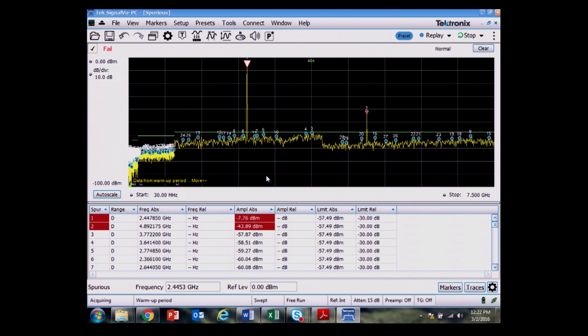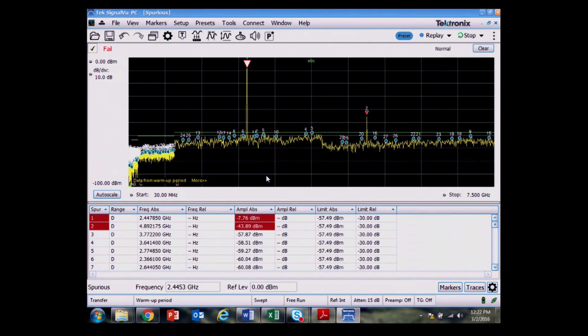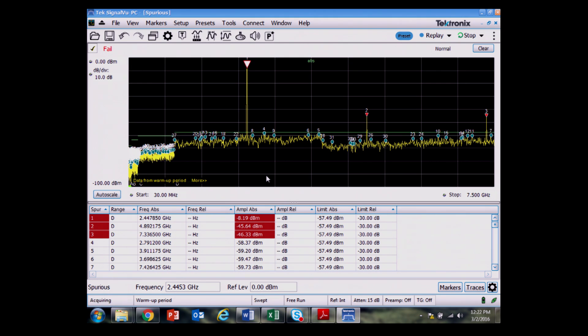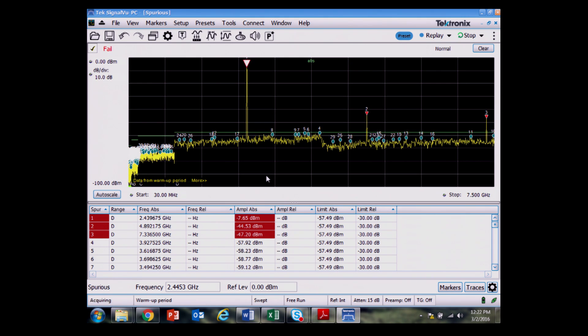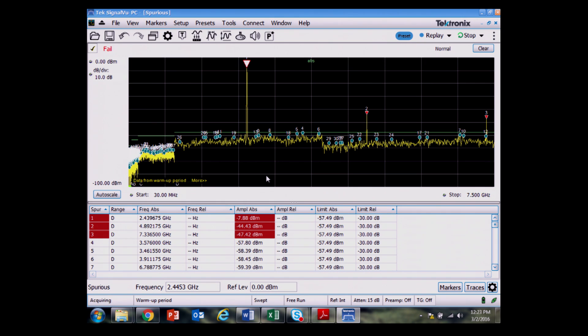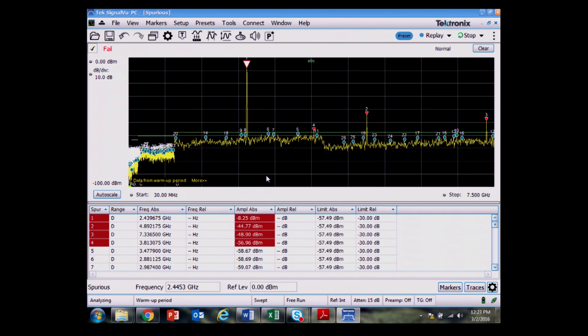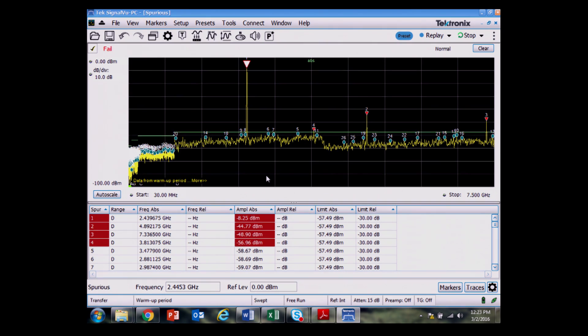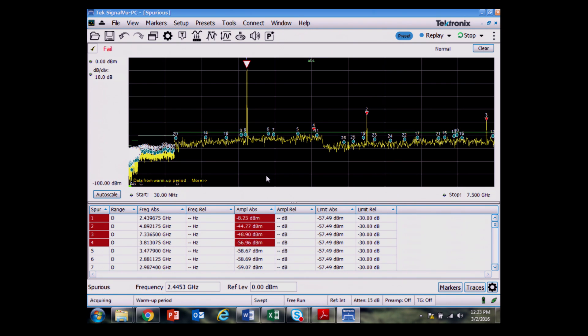This is typically a test that would be done over a broad frequency range. You can see this is done up to 7.5 GHz for EMI pre-compliance. As long as I have the setup done correctly and I'm in some sort of quiet RF environment, there's not background noise interfering with this, then this should give me reasonably good assurance that I'd pass the test.